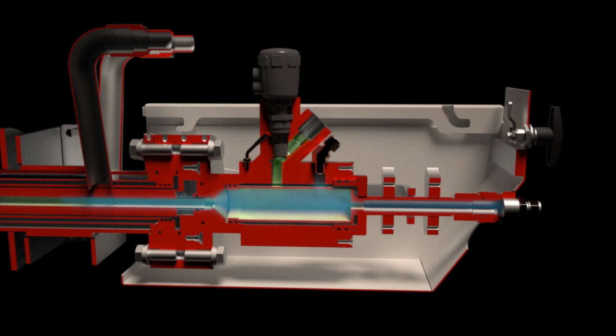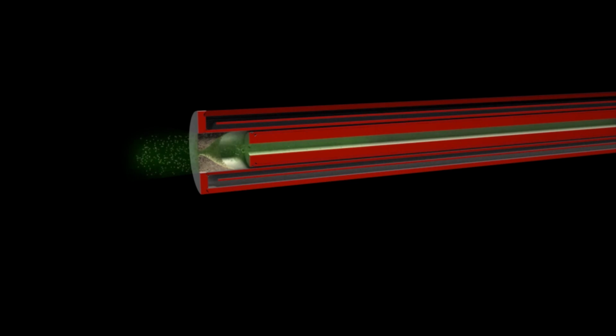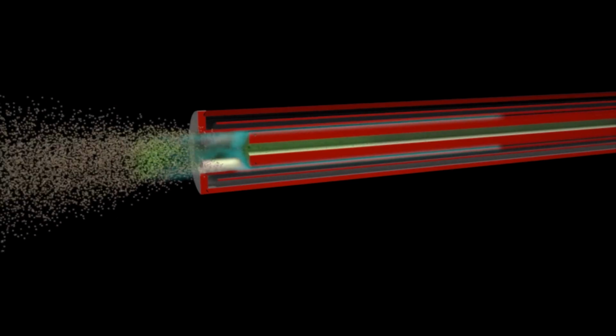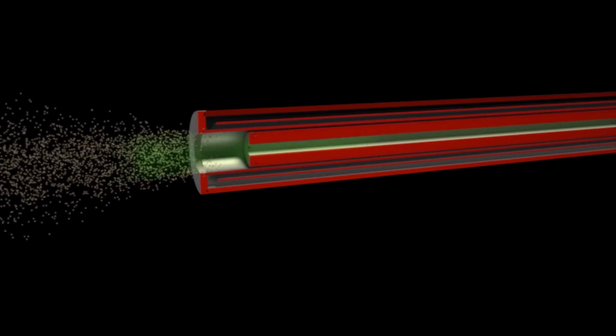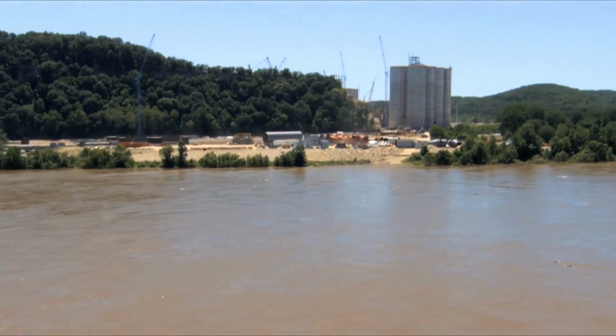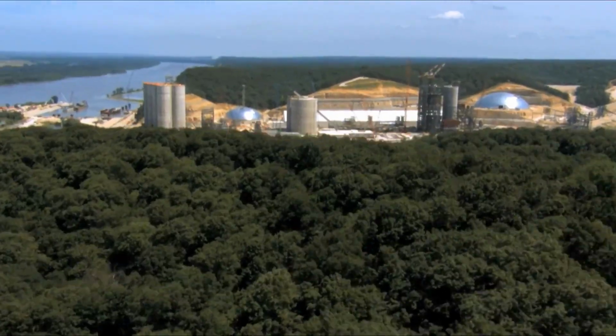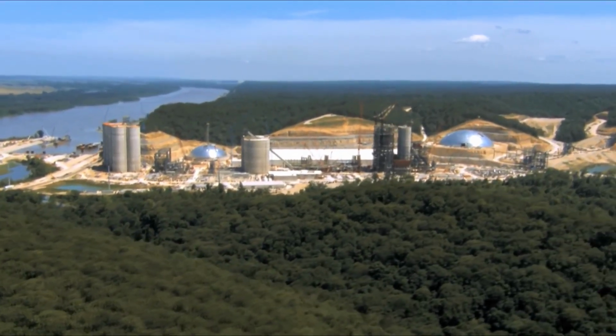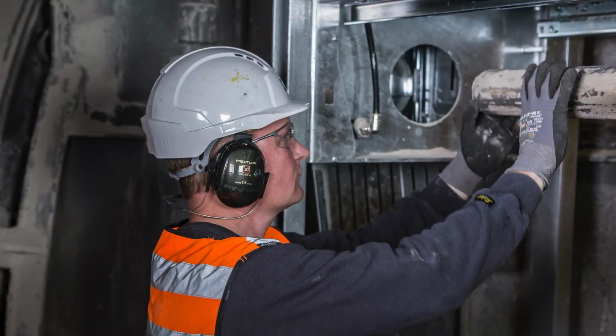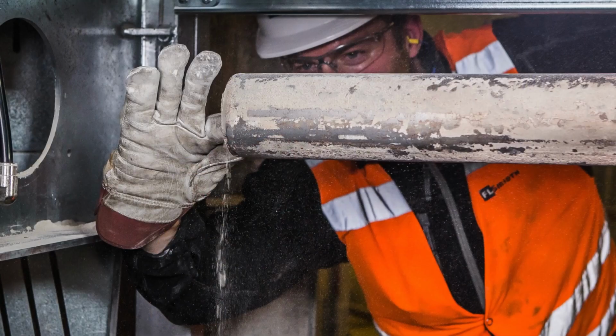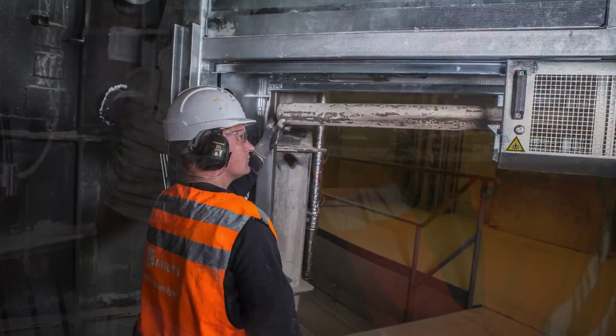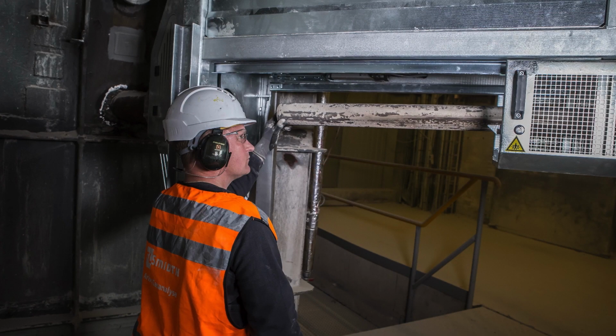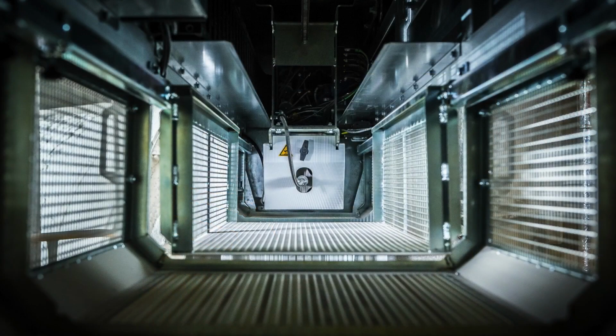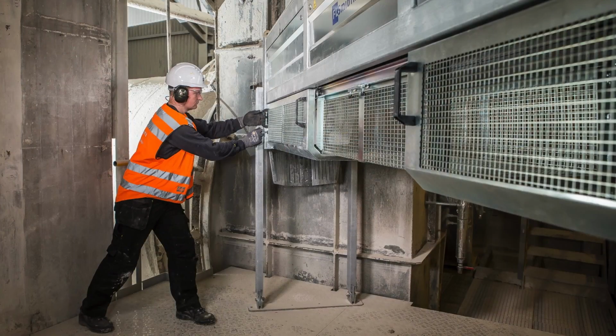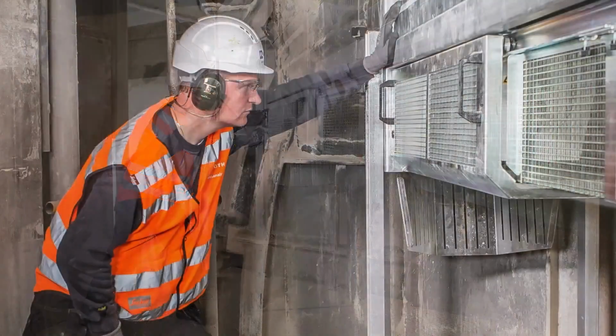The probe is cleaned automatically using jets of compressed air to blast dust and residue out of the sample path in one go. And its one-pipe design, with no kinks or bends, ensures that the probe and filter stay clean for longer. However, despite some manufacturers' claims, all gas analysis systems will get blocked at some stage or another. The difference with the KilnLoq probe is the easy access to the probe tip for manual cleaning. And it takes just 1 to 3 minutes for a full clean from the back end of the probe, compared to 30 to 120 minutes for conventional systems.